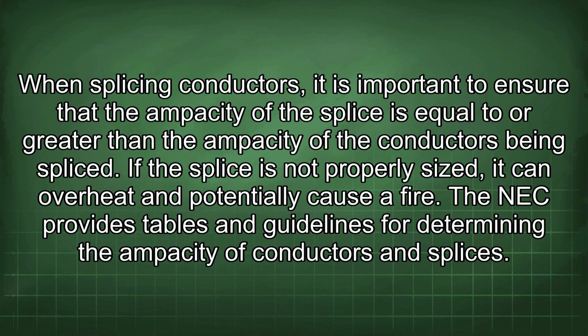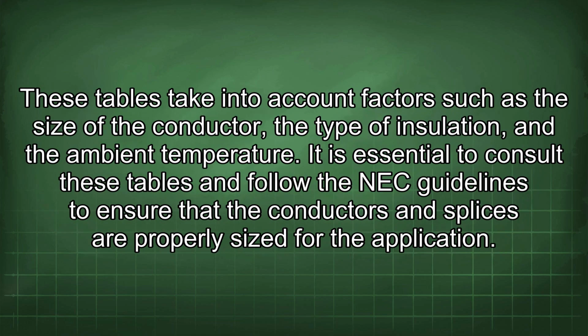The NEC provides tables and guidelines for determining the ampacity of conductors and splices. These tables take into account factors such as the size of the conductor, the type of insulation, and the ambient temperature. It is essential to consult these tables and follow the NEC guidelines to ensure that the conductors and splices are properly sized for the application.